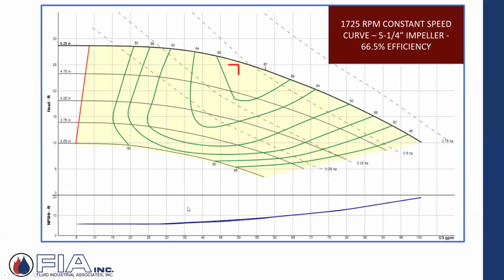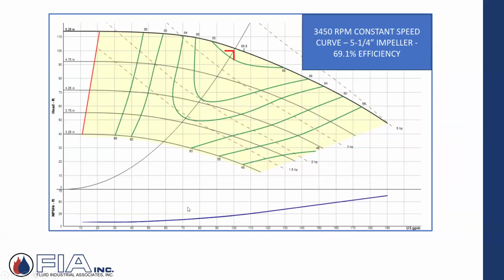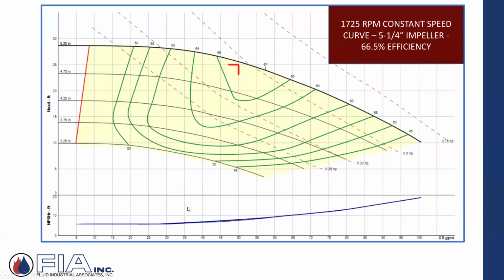And I cut that flow rate in half, kind of just following along with that pump affinity law, the relationship or the ratio when I change the speed, how it impacts flow. I could pick the same pump, but just pick it with a 1725 RPM motor and with the same impeller diameter. So I didn't change it, I just changed the speed. I will have a flow rate of 50 gallons a minute and a pressure differential of about 25 feet of head, which falls in line with the pump affinity law: change the speed, the flow rate is a 1-to-1, and the relationship on the head is squared. So back here, 100 gallons a minute, 100 feet of head, cut it in half by cutting the speed in half, 50 gallons a minute flow, and a quarter, 25 feet of head. So same pump, two different motors, just following that pump affinity law.